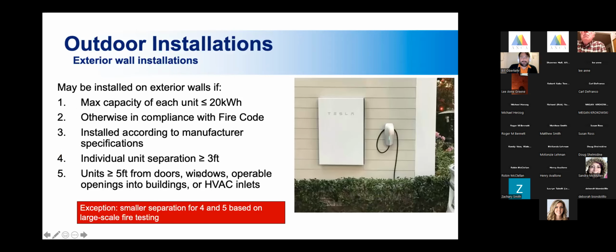For outdoor installations, this is all the same information that was in the residential code. In fact, in the fire code, as it pertains to one and two family homes, it's almost verbatim what the residential code section says. So duplicative, but I just want to highlight once again, individual unit separation and separation from doors, windows, and that sort of thing. Again, based on large scale fire testing. So we've got 3 feet unit separation and 5 feet from doors and windows in the fire code. If the large scale fire testing, the 9540A report, says that you don't need 3 feet or you don't need 5 feet, then you do not need that. That is how large scale fire testing works, and that is its purpose.